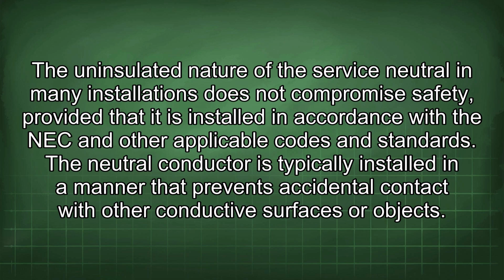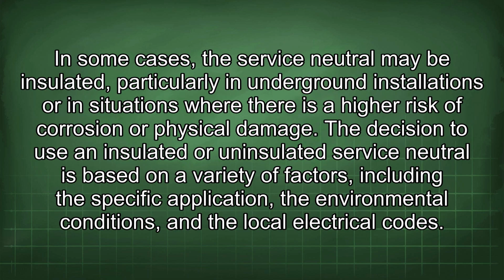The uninsulated nature of the service neutral in many installations does not compromise safety, provided that it is installed in accordance with the NEC and other applicable codes and standards. The neutral conductor is typically installed in a manner that prevents accidental contact with other conductive surfaces or objects. In some cases, the service neutral may be insulated, particularly in underground installations or in situations where there is a higher risk of corrosion or physical damage.